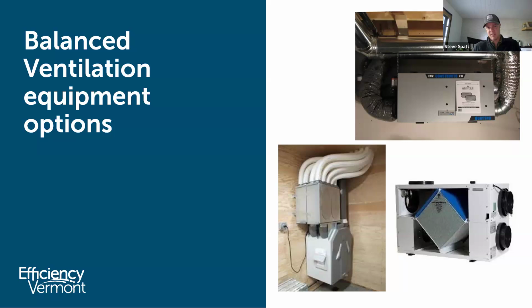Because the higher the fan speed and the more air moving through the ductwork, the noisier the ducts will be, the noisier the system will be. You'll also be minimizing your sensible recovery efficiency through the heat core, because you're moving more air across it than it wants to see. You have higher energy penalties there. So trying to design within the middle range of the capacity of the equipment is critical.